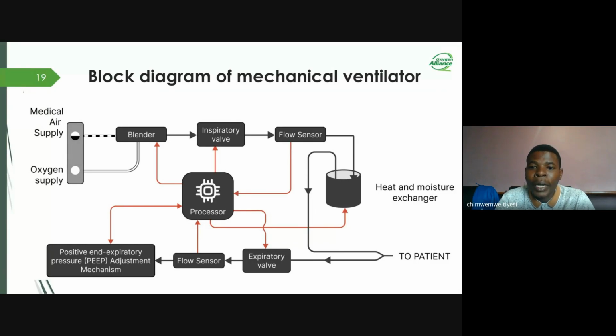From here, the fresh gas goes into a humidifier or the heat and moisture exchanger, which adds moisture and heats up the air to match the body temperature. Then the fresh gas travels through one of the Y connector legs to the patient. From the patient, the expiratory valve opens to let the exhaled gas exit the patient's lungs. Additionally, there is a PEEP valve. Some just call it PEEP. In full, it's called a positive end expiratory pressure adjustment mechanism or valve. This valve controls the pressure in the patient's lungs at the end of exhalation.